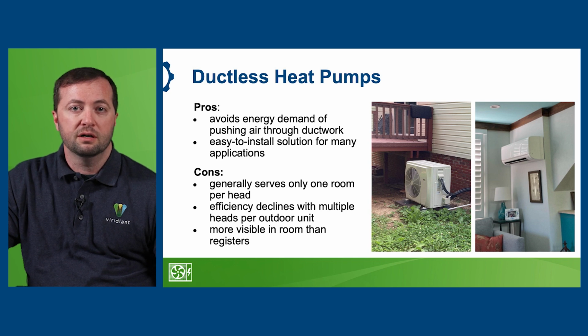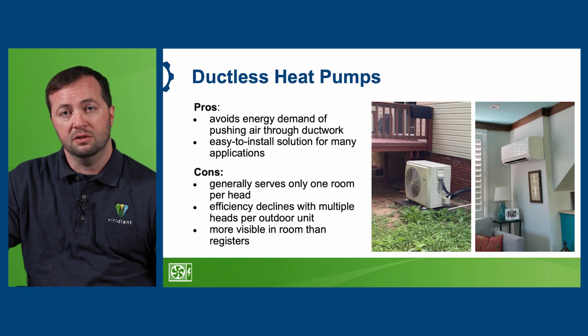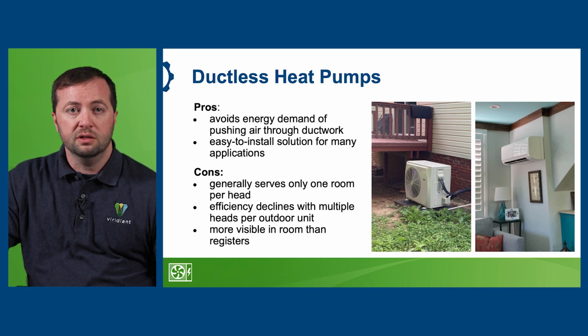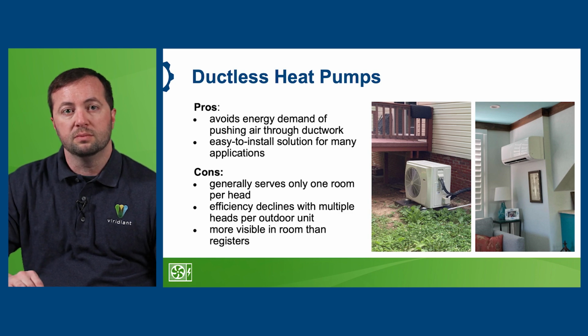When serving an entire conventional home with these, the primary downside is that there's more equipment that needs to be maintained, purchased, and eventually replaced. Generally, you'll need a head, what we call the inside unit, in each room. Those heads only come in certain capacities, and much of the time the smallest capacity is still going to be too large for the heating and cooling needs of an individual room, so you'll end up with oversizing. Generally, a ducted system is best for a typical home with lots of individual rooms.